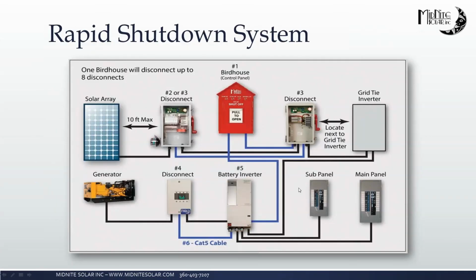This is just an example showing how it would work electrically. The black is the power, the blue is the communications. The birdhouse does require its own communications cables between everything. It is an Ethernet-based pinout, but we try not to call it Ethernet cable because that typically indicates some form of digital communications. The birdhouse uses all low voltage, low current analog signals, so we're only using the pinout for your convenience. We're using the cable as DC communications. This is also showing how you could isolate a generator.